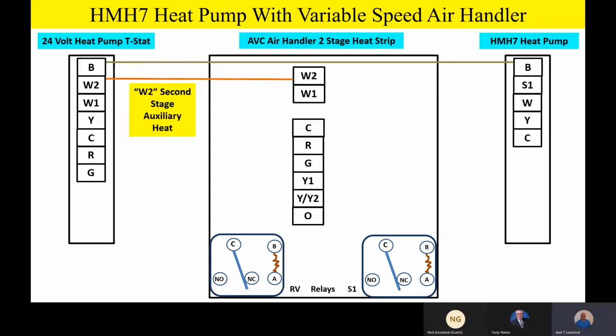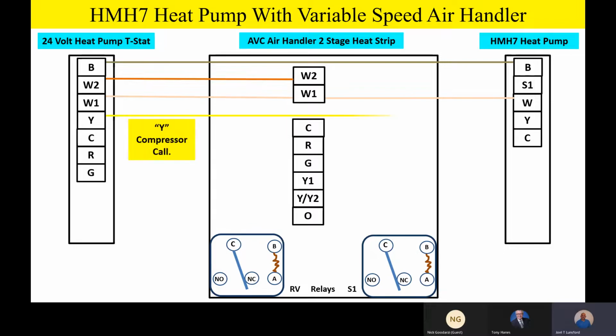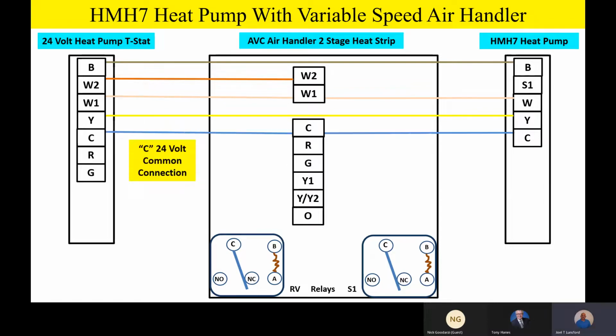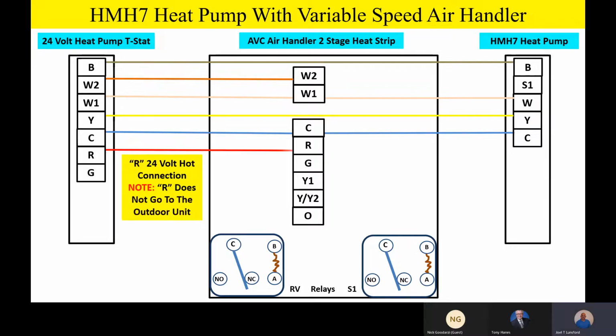W2 is our second stage auxiliary heat. W1 is our first stage of auxiliary heat if you have a two-stage heat strip in the air handler. And that W1 is going to go outside as well to bring the heat strip on during defrost if you have a heat pump application outside. The Y terminal goes all the way through like we did before. The C terminal goes all the way through just like we did before. The R terminal goes to the air handler and stops at the air handler, because remember, we don't take R outside with the HMH7 heat pump.